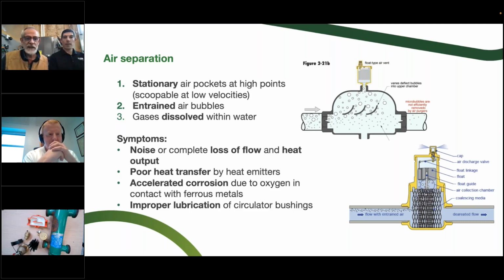Yeah, back in the day, the old cast iron boilers were air separators. In fact, some of them even had little sections with little vanes and fingers in there to try and encourage air. And all you did is screw an air vent right through the jacket in the top, and it did a pretty good job of getting air out. But that's not the case with a boiler like the one behind me that holds 1 gallon of water, and it's going through there pretty fast to keep the velocity up, to keep that heat exchanger. So, you know, high efficiency equipment needs high efficiency air and dirt removal. That's the bottom line to it.